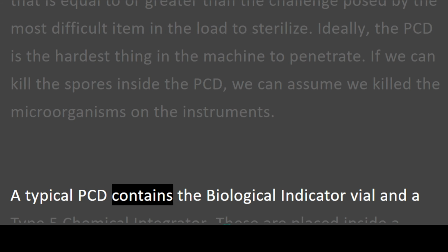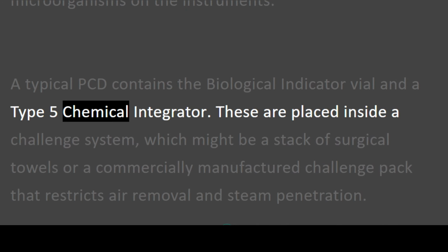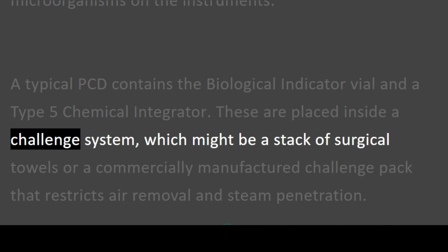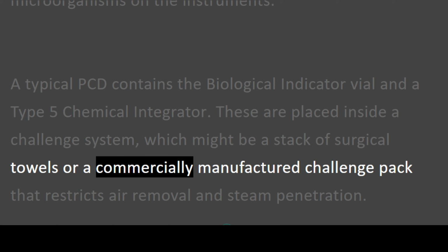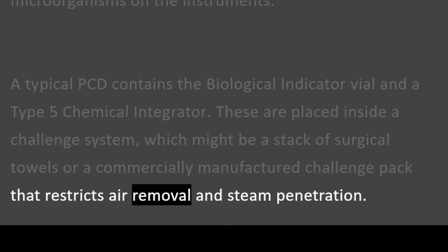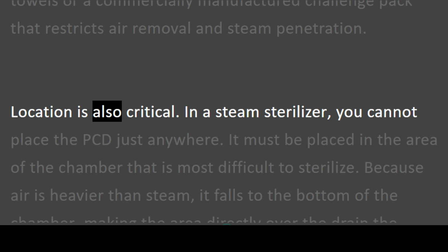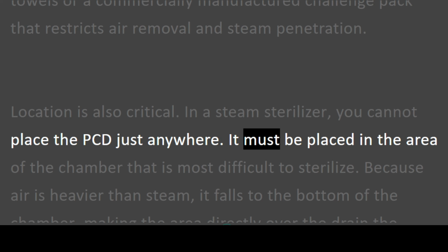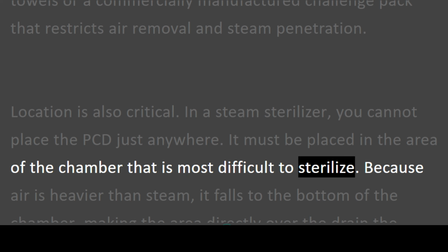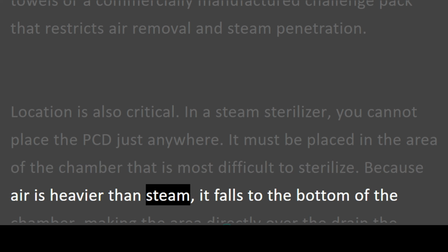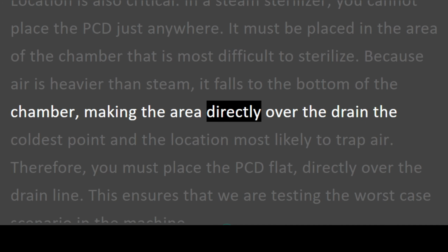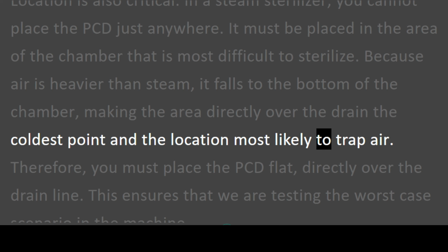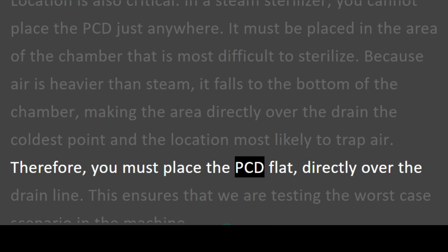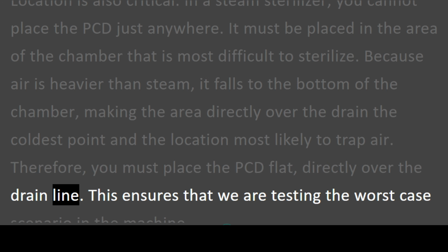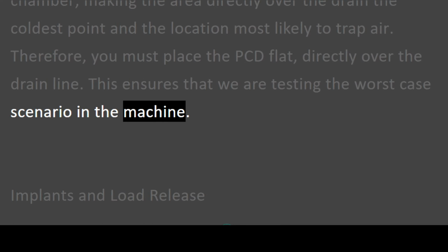A typical PCD contains the biological indicator vial and a Type 5 chemical integrator. These are placed inside a challenge system, which might be a stack of surgical towels or a commercially manufactured challenge pack that restricts air removal and steam penetration. Location is also critical. In a steam sterilizer, you cannot place the PCD just anywhere. It must be placed in the area of the chamber that is most difficult to sterilize. Because air is heavier than steam, it falls to the bottom of the chamber, making the area directly over the drain the coldest point and the location most likely to trap air. Therefore, you must place the PCD flat, directly over the drain line. This ensures that we are testing the worst-case scenario in the machine.